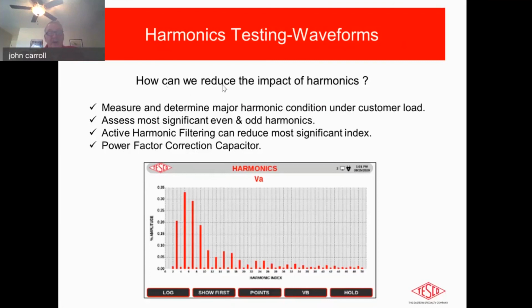And the active harmonic filtering also is now very much a part of transformers. Many of you out there might be familiar with K-factor rated transformers. They are designed from the beginning to accept a level of harmonic conditions on the circuits, which means they don't overheat. They have active filtering in there. So again, these are all ways that we can reduce the impact. It's very difficult and very expensive to try and eliminate them. And I think we can live with them up to a point, but this is a way we can actually help.